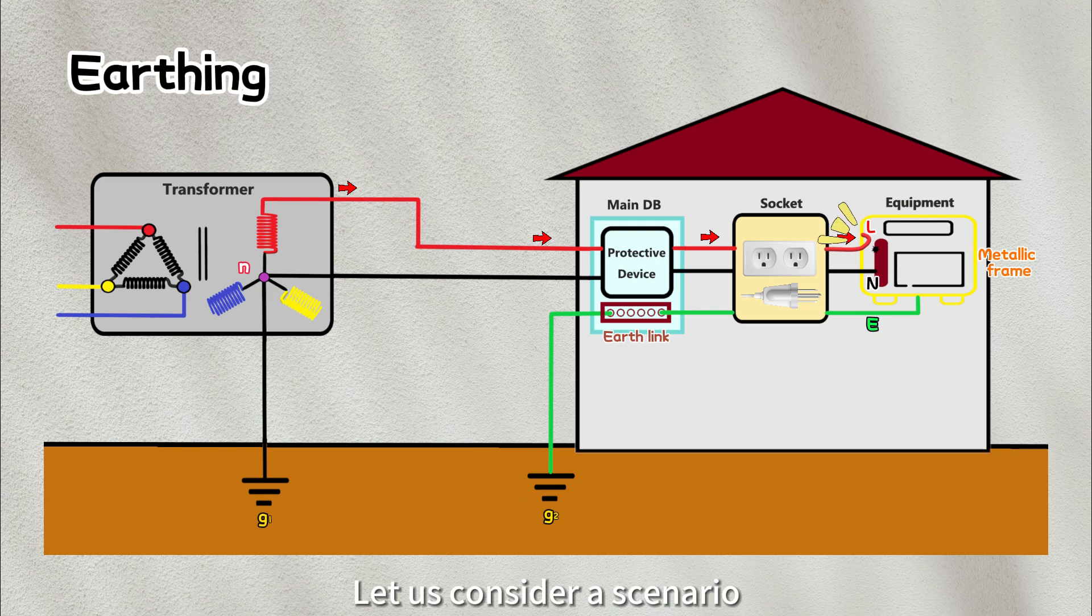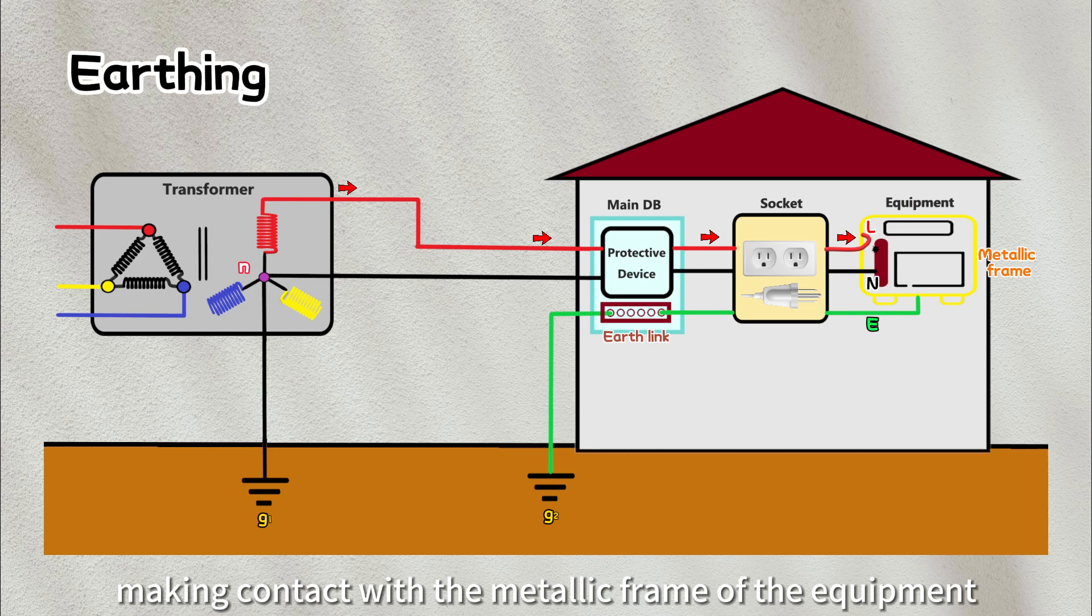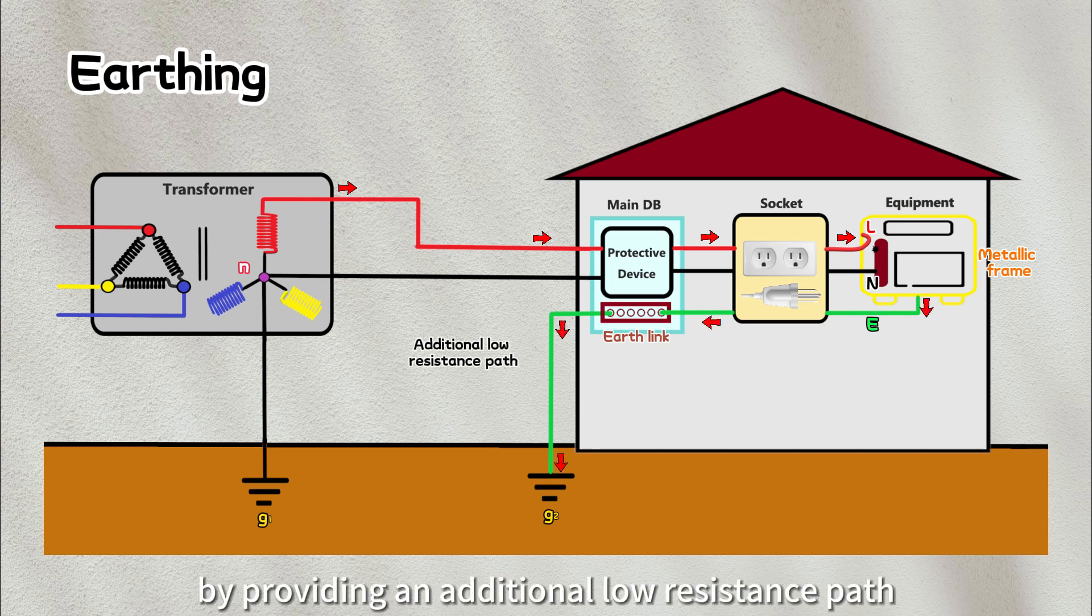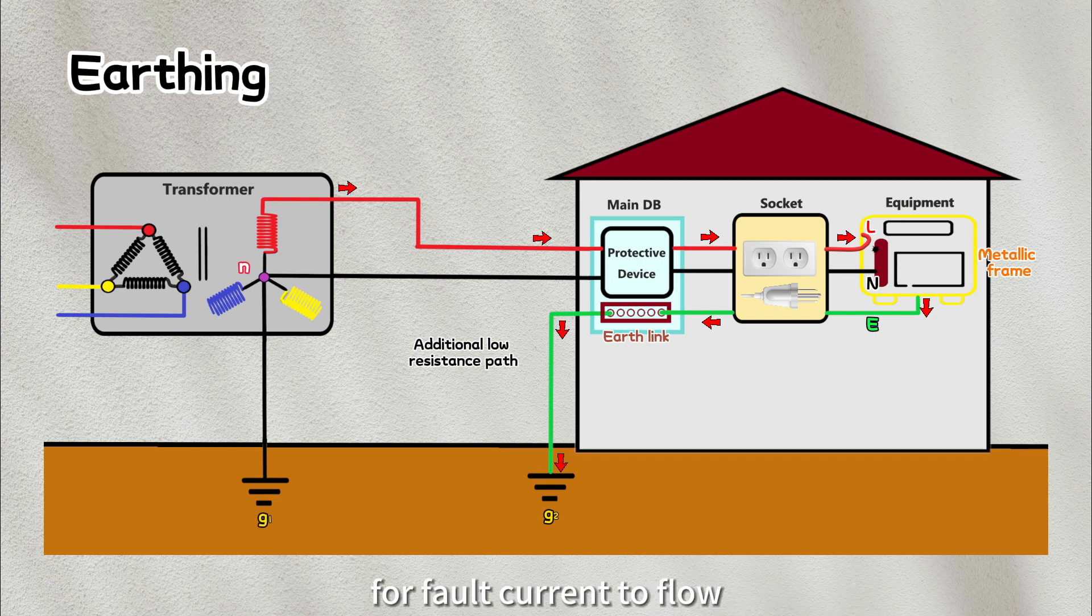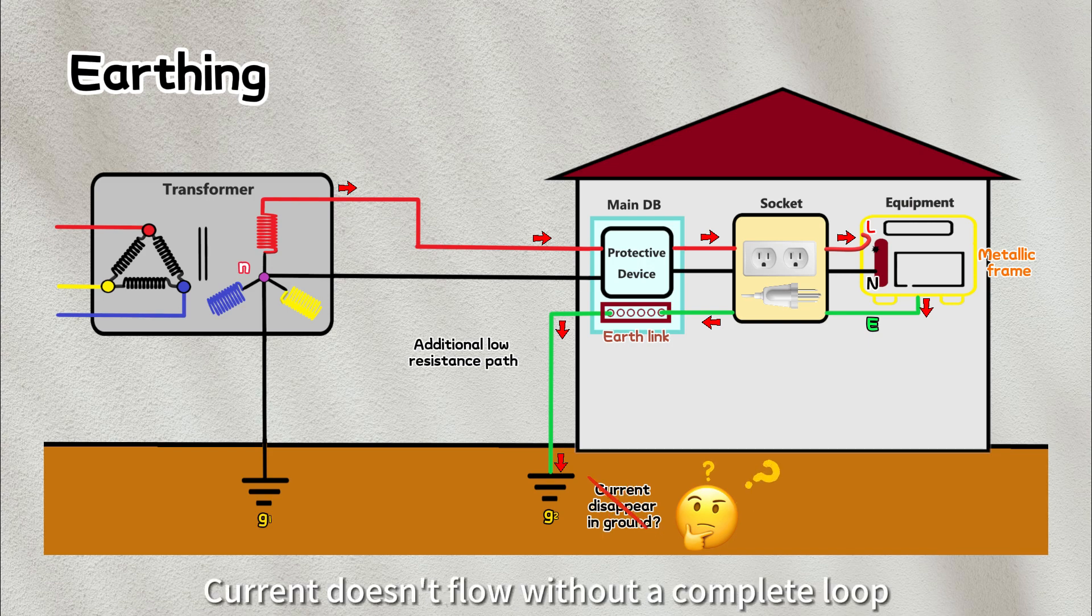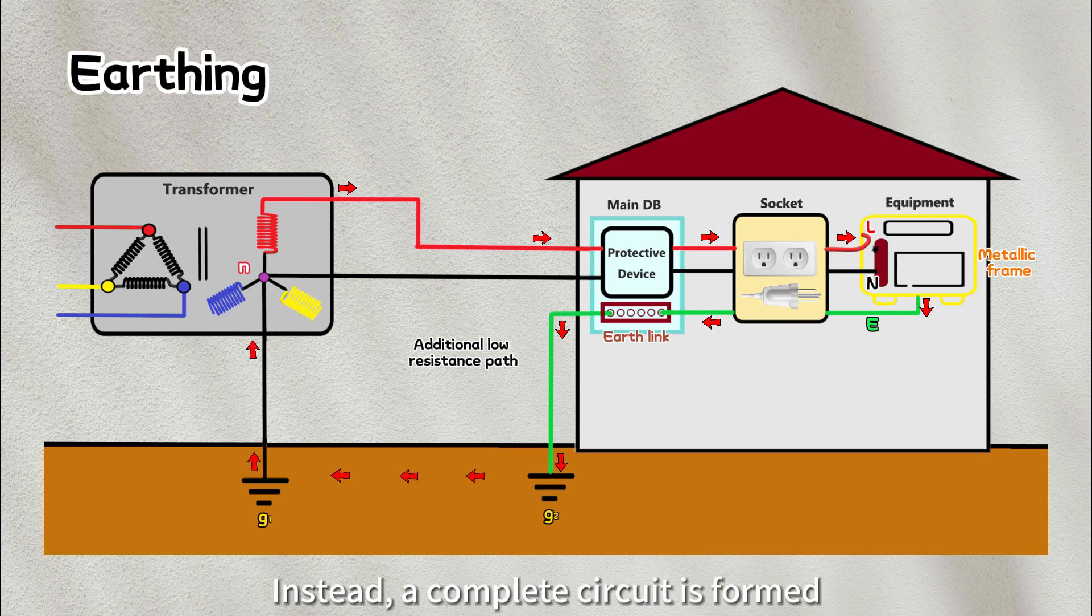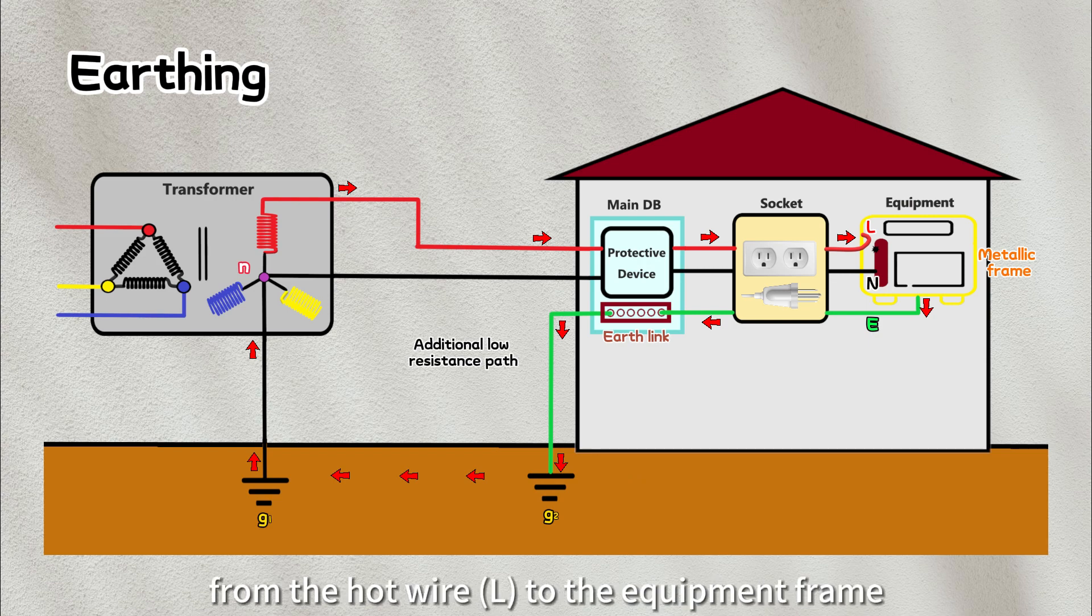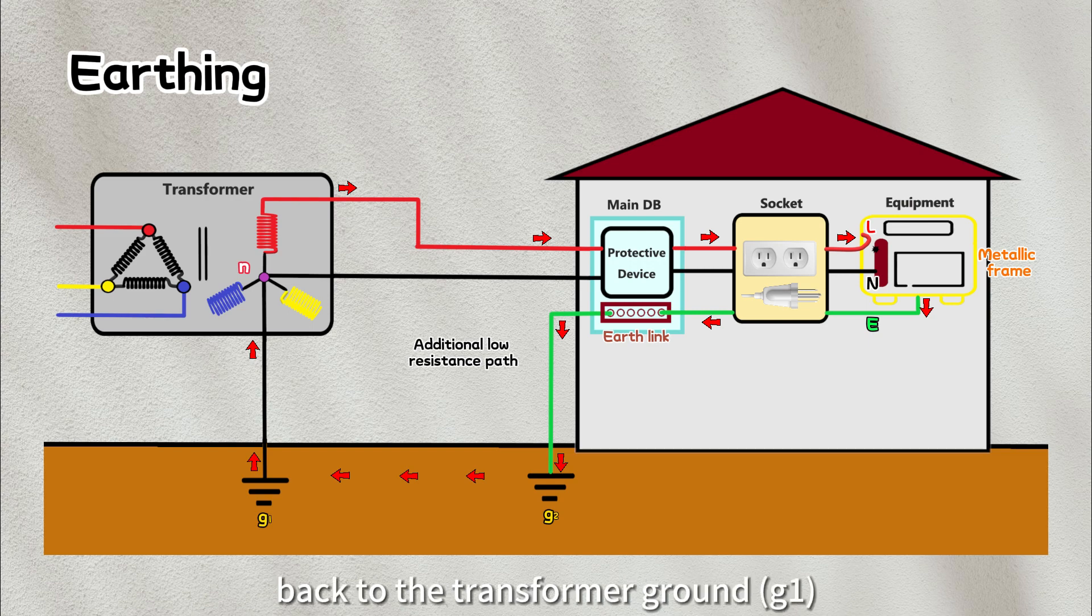Let us consider a scenario where the live wire becomes loose or breaks, making contact with the metallic frame of the equipment. Now the earth wire steps in to lower the risk of electrocution by providing an additional low resistance path for fault current to flow. You might wonder if all the fault current will simply flow through the earth wire into the ground and disappear. The answer is no, current doesn't flow without a complete loop. Instead, a complete circuit is formed from the hot wire to the equipment frame, then through the earth wire to the earth rod into the ground, back to the transformer ground, and finally to the neutral point.